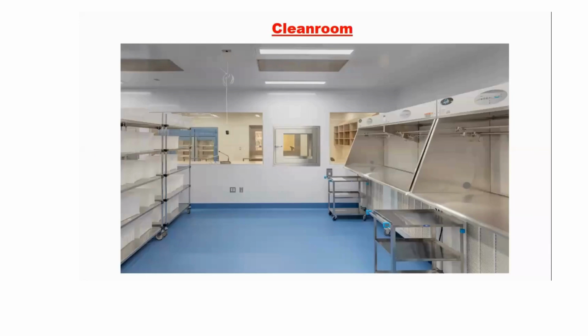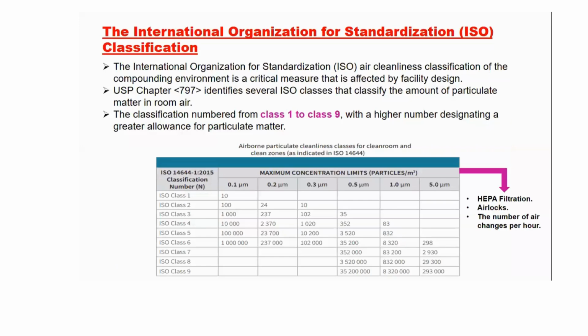This is an example of a clean room that contains two primary engineering controls. When we talk about the sterile compounding environment, we must mention the ISO classification. The ISO air cleanliness classification of the compounding environment is a critical measure that is affected by facility design. United States Pharmacopoeia Chapter 797 identifies several ISO classes that classify the amount of particulate matter in room air.